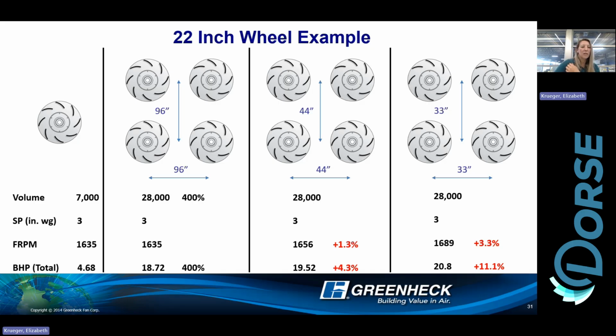So here's an example of a 7,000 CFM at 3 inches of static pressure. That's our one wheel. That's the brake horsepower required to spin that wheel. So now when we put 4 of them together, we have 28,000 CFM at 3 inches of static. And with the spacing of 96 inches apart and wide, we have no translation, no communication happening, no losses happening from the air bumping into the air coming off the other wheel. Now, when we start decreasing that, 44 inches is where our testing led us to start seeing some changes in that fan performance.